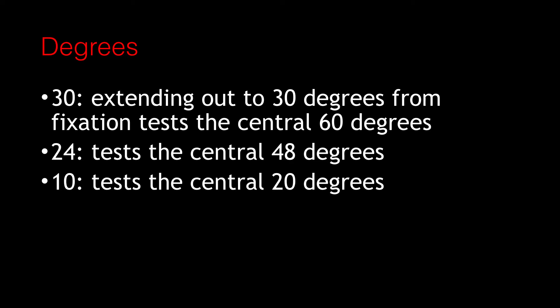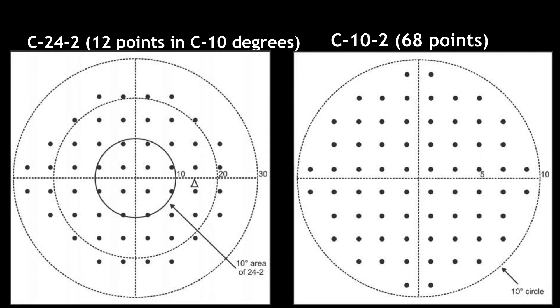In 30 degrees, we are checking the central 60 degrees because it extends out 30 degrees from fixation. In 24-2, we are checking the central 48 degrees, and in 10-2, we are checking the central 20 degrees.